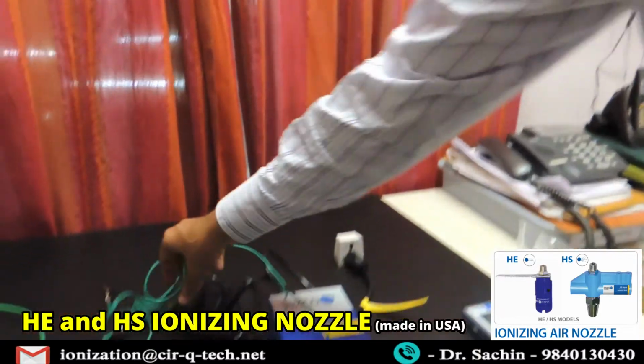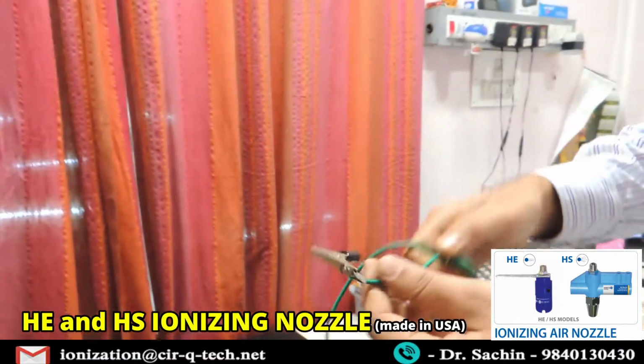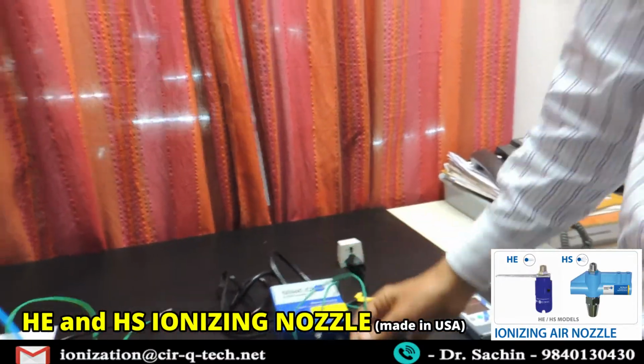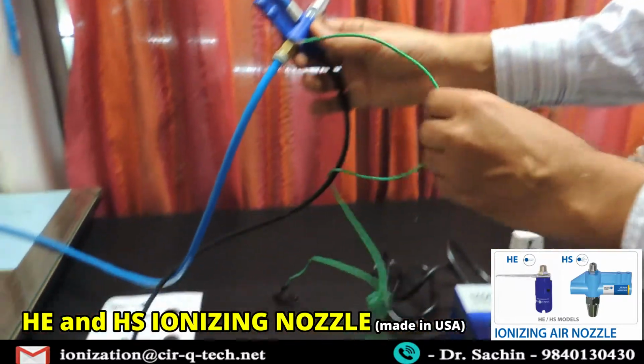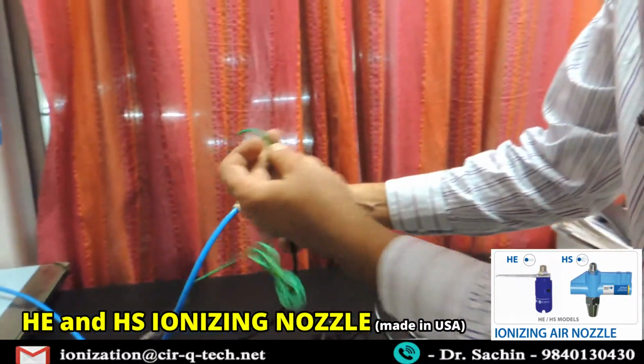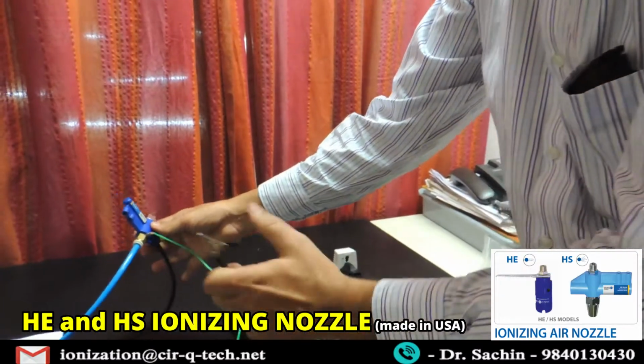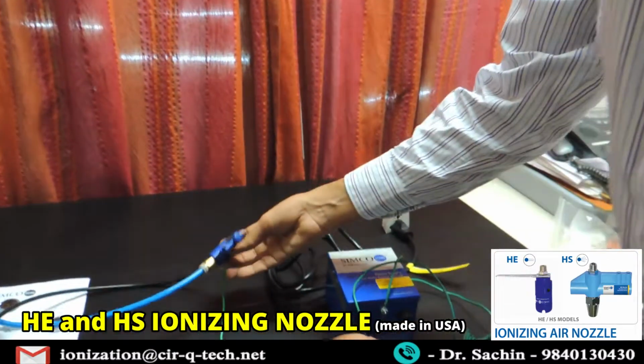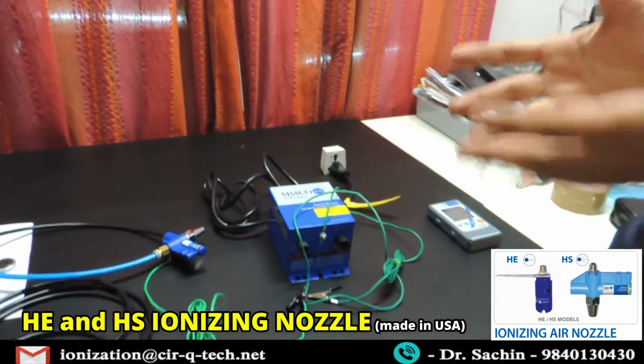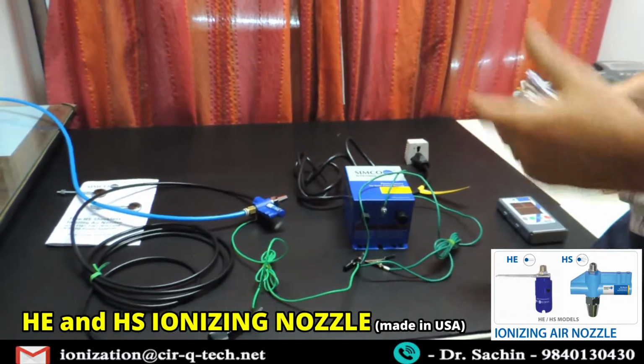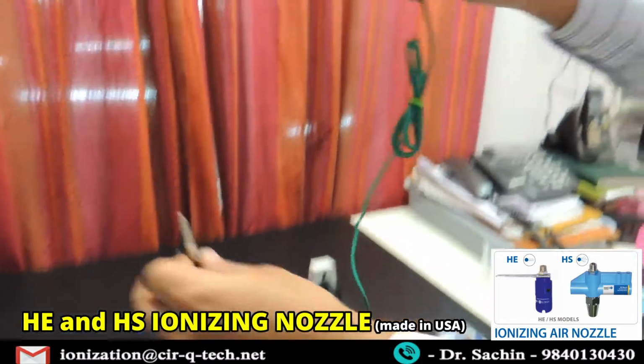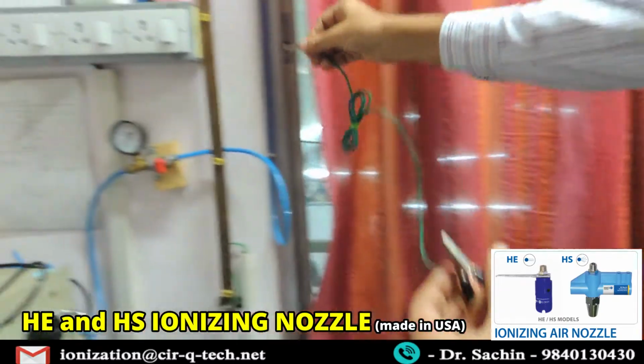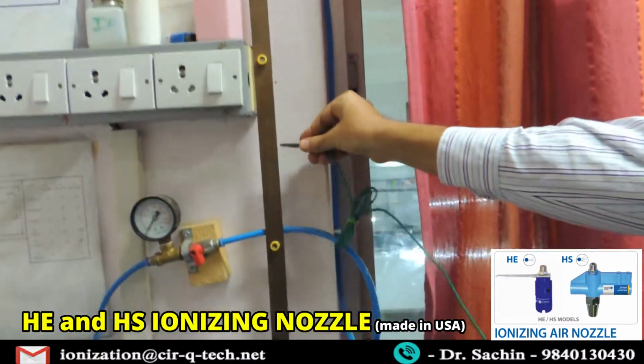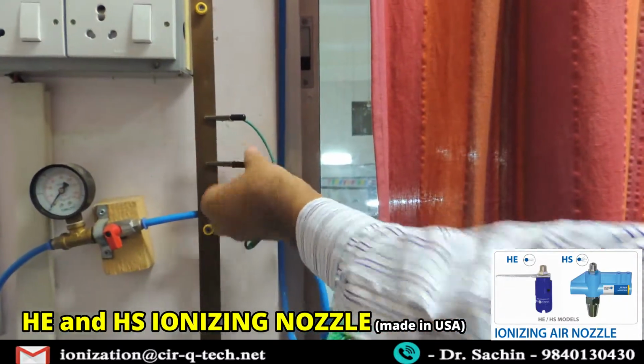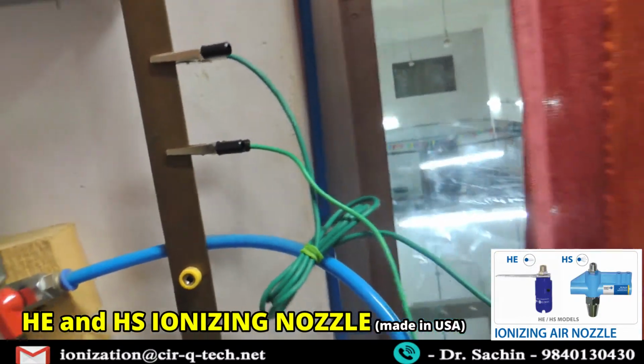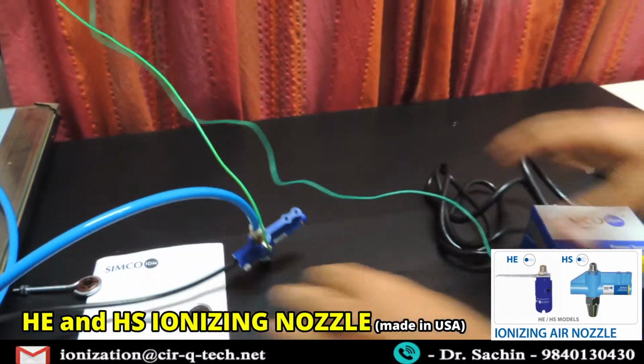Earthing is very necessary. I have now made temporary arrangements of grounding the power supply and grounding the nozzle separately. So these two are very necessary. If you do not give any grounding or earthing, a risk of shock is there, which is obviously very mild, but the main thing is the ionization doesn't take place unless you do the proper earthing. So we have a bus bar here where we should be connecting it for earthing. This is just a common bus bar which goes to an earth pit outside. So this way both the nozzle as well as the power supply are connected to the earth.